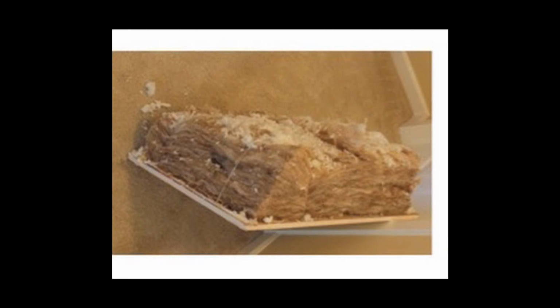So you as a contractor have to use your imagination in insulating the top of an access panel. And I would suggest that you think about a foam board insulation up there, something that will withstand some rough handling. But keep in mind that some foams are not fire rated, and they have to be protected from the interior space by some kind of a fire barrier, such as a half-inch drywall or a cement board adhered to the top of the plywood access panel.